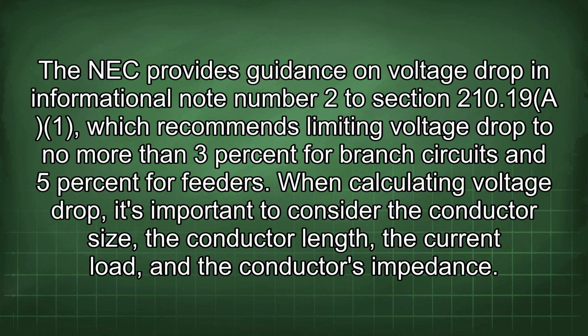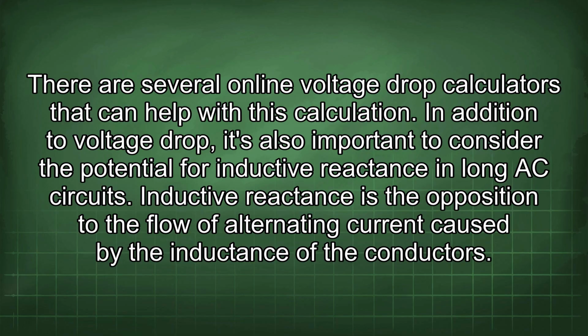The NEC provides guidance on voltage drop in informational note number 2 to section 210.19(A), which recommends limiting voltage drop to no more than 3% for branch circuits and 5% for feeders. When calculating voltage drop, it's important to consider the conductor size, the conductor length, the current load, and the conductor's impedance. There are several online voltage drop calculators that can help with this calculation.